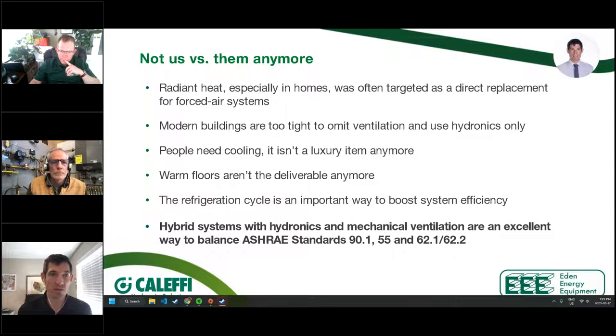You know, commercial buildings for sure have tighter standards, as described on the bottom with ASHRAE standards 90.1, 55 for thermal comfort, and then 62.1 for commercial ventilation standards. We have to move some air around the building. So it isn't like we can just say we're only doing hydronics, we're not moving any forced air. People want cooling. We need to get the stale air out of there. That's just the reality that we live with.